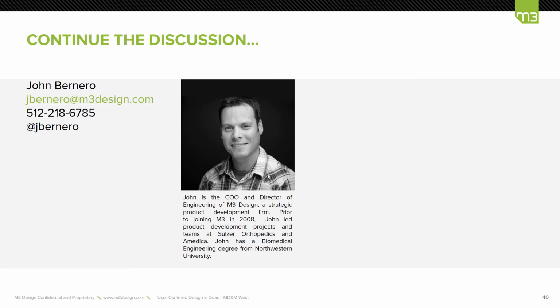So the journey map is separate from your design requirements, and I think that's where the prioritization is. As you identify the different stakeholders and their needs, it comes down to what the FDA is looking for: what's safe and effective. They don't care if you make money. They don't care if you deliver a good user experience. What they care is that you don't hurt anyone or harm anyone. So keep that in mind when you're developing, and identify some things you might be looking at more from a business perspective, or you're trying to deliver a better customer experience than maybe your competition or otherwise.